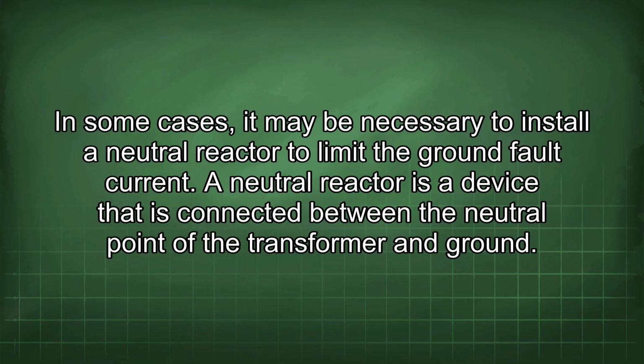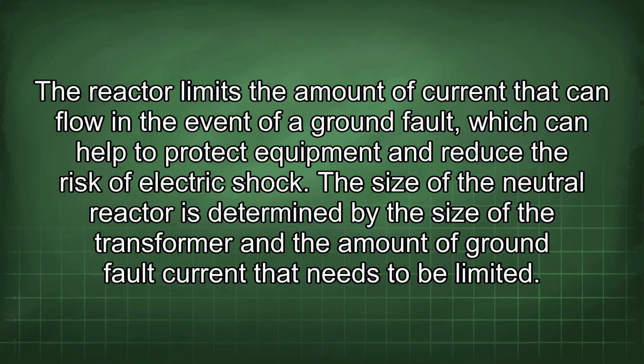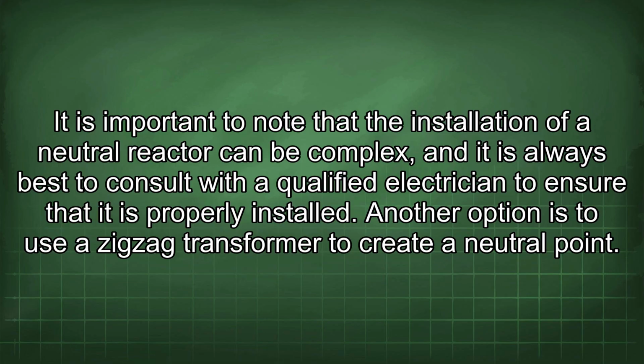In some cases, it may be necessary to install a neutral reactor to limit the ground fault current. A neutral reactor is a device that is connected between the neutral point of the transformer and ground. The reactor limits the amount of current that can flow in the event of a ground fault, which can help to protect equipment and reduce the risk of electric shock. The size of the neutral reactor is determined by the size of the transformer and the amount of ground fault current that needs to be limited. It is important to note that the installation of a neutral reactor can be complex, and it is always best to consult with a qualified electrician to ensure that it is properly installed.